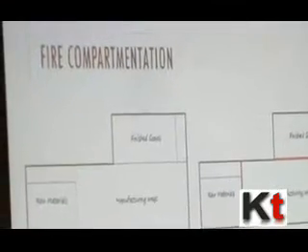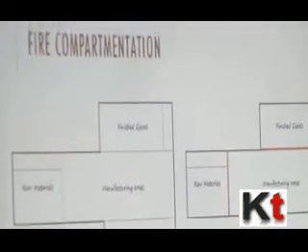So how do you do it? When you develop your plans, you look at areas which you need to occupy and identify the fire loads. So what is more, what is less. Identify the value of your equipment where it is kept. Then segregate it. It's a simple, low-cost intervention which can save really millions. And if possible, you can push away your utilities from the manufacturing areas. That separation itself will give you the required protection, because utilities will definitely have fuel and high energy.